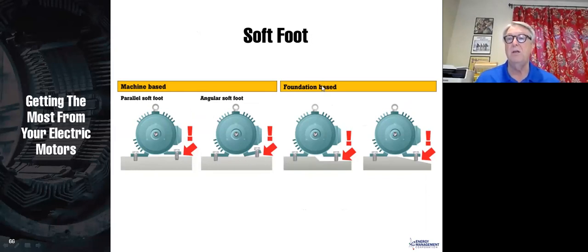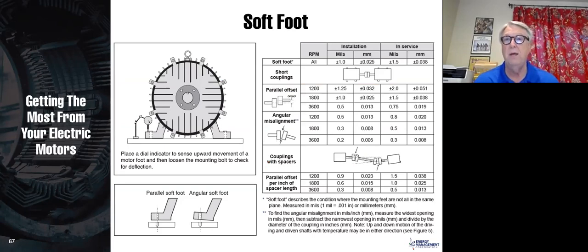That is the machine. The foundation is the more common problem. You could have the foundation, as you see over here, at a different height or slanted. So it's very important that you get a good solid foot on the machine, as a soft foot is going to allow that machine to vibrate and lead to premature failure.